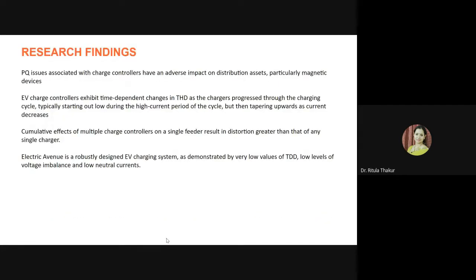So what are the major research findings of this? The major research finding was that the power quality issues which are associated with charge controllers have an adverse impact on distribution assets, particularly magnetic devices such as power transformers, cables, metering devices, switchgear, and fuses. And then EV charge controllers exhibit time dependent changes in THD as charging progresses during the charging cycle.